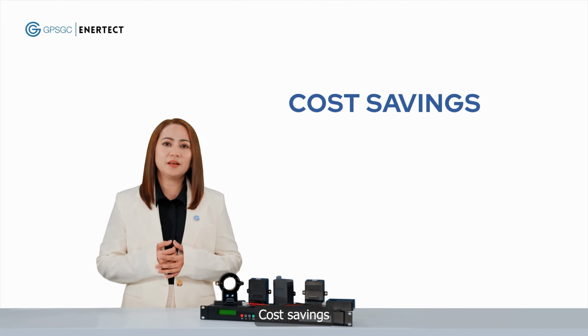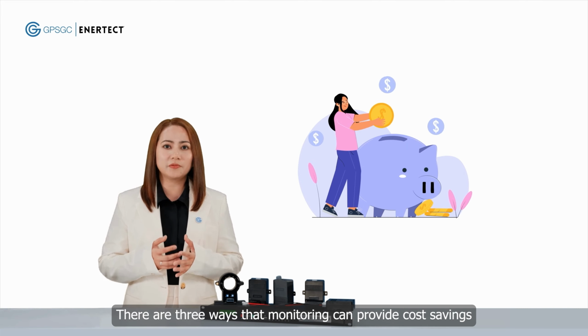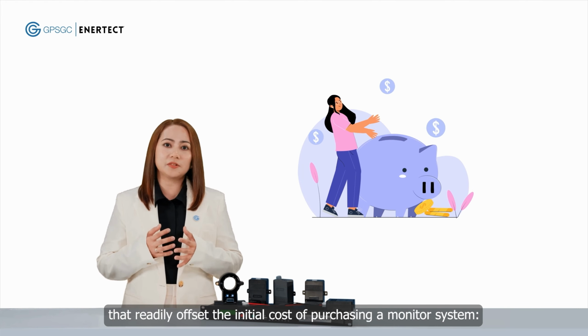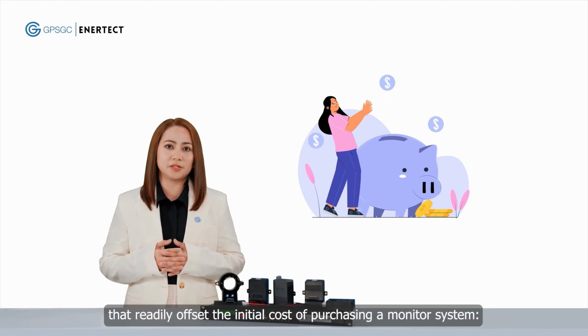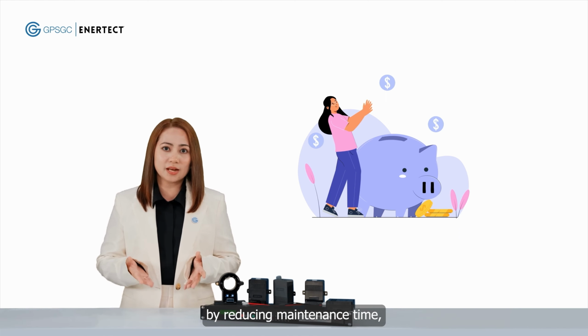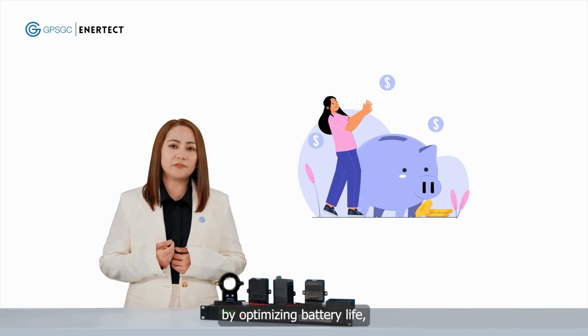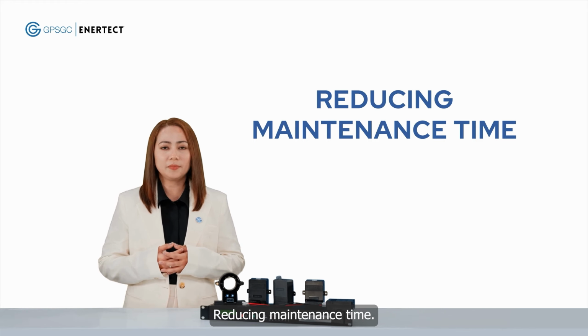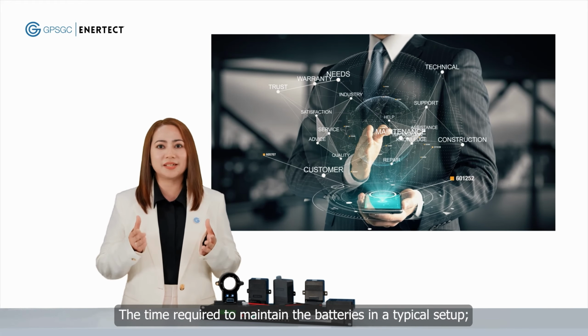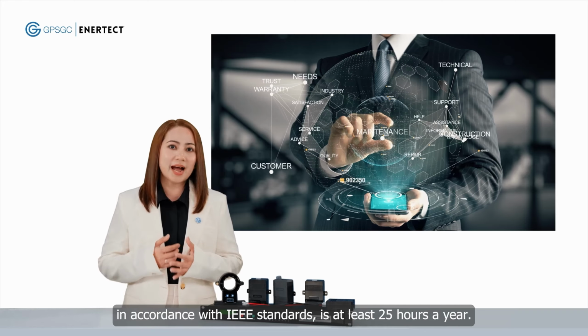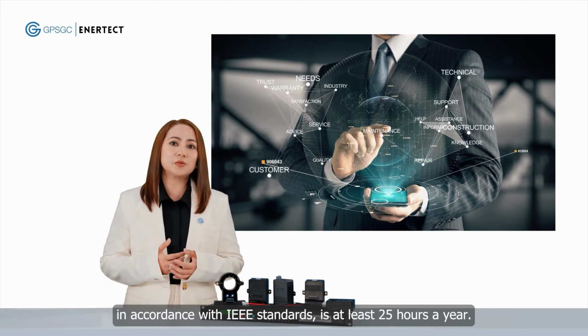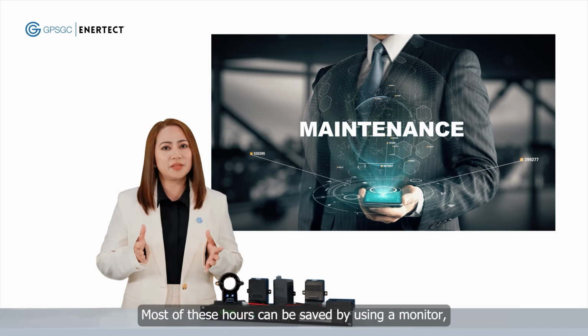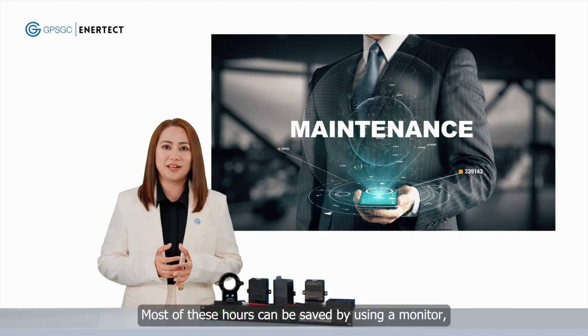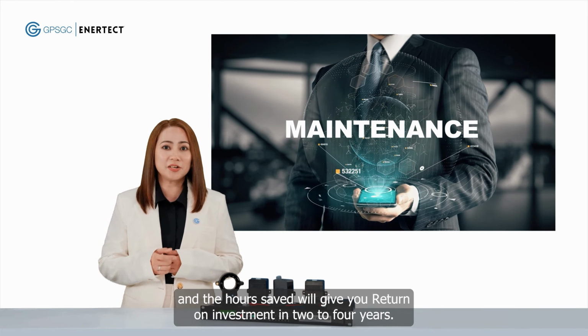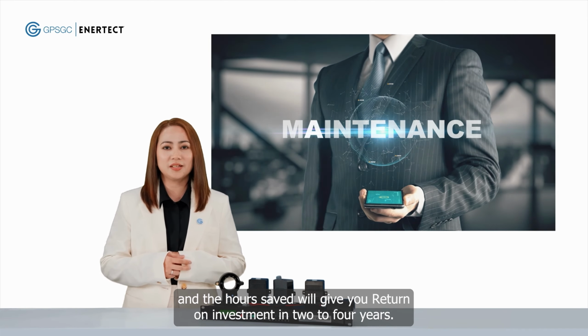Cost savings. There are 3 ways that monitoring can provide cost savings that readily offset the initial cost of purchasing a monitor system: by reducing maintenance time, by optimizing battery life, and by reducing test costs. Reducing maintenance time. The time required to maintain the batteries in a typical setup, in accordance with IEEE standards, is at least 25 hours a year. Most of these hours can be saved by using a monitor, and the hours saved will give you a return on investment in 2 to 4 years.